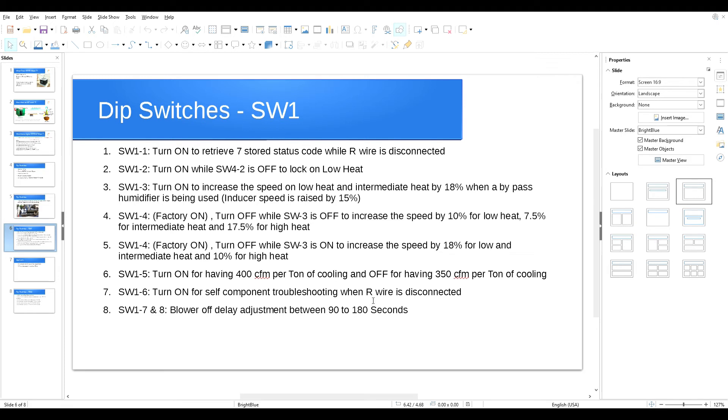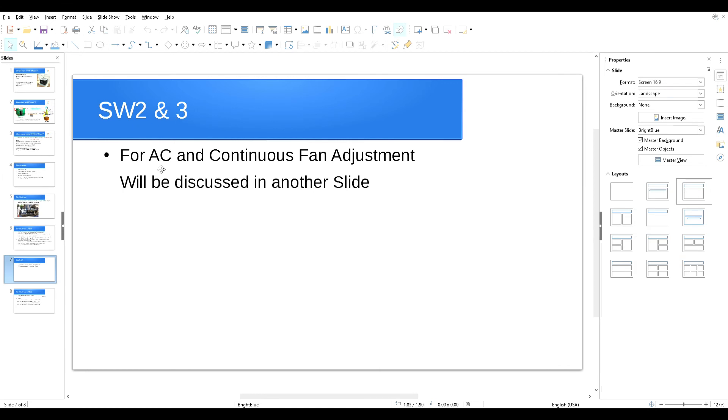SW1 switch number six: disconnect the R terminal on the furnace control board, then turn the switch on and the system will self-troubleshoot. If a part or component is not working, the LED starts flashing and tells you the error code, which you can find on the furnace door. SW1 switches number seven and eight are for blower-off delay adjustment between 90 to 180 seconds — not critical, just leave those at the factory setting.